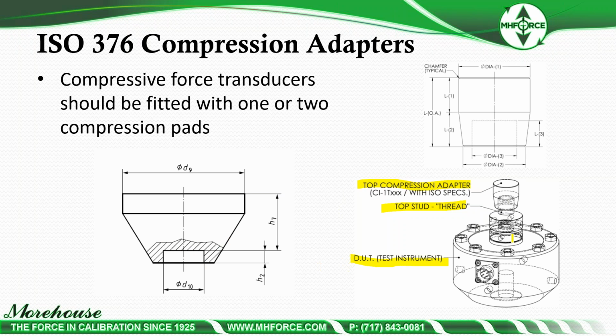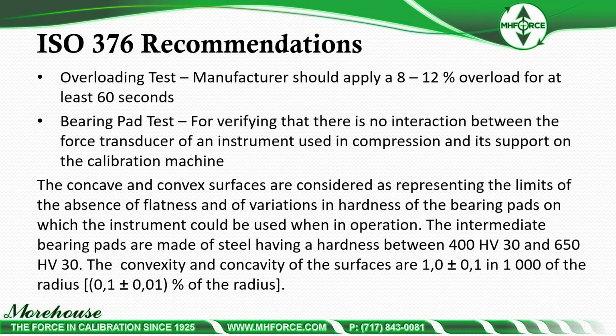The tension ones, the results are much greater as far as improvements. But the compression ones, again, if you're using an adapter that's a different hardness than what the lab's using, the measurement could be off by 0.5% on some load cells. Additional ISO 376 recommendations. Overload test, manufacturer should apply 8 to 12% overload for at least 60 seconds.